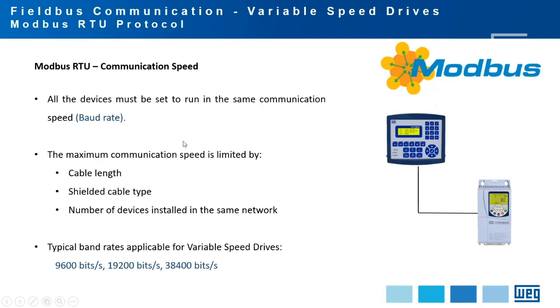Regarding communication speed, Modbus RTU requires all devices to use the same baud rate. The speed may vary according to cable length, cable type and shielding quality, and the number of devices in the network. Typical baud rates for variable speed drives go up to a maximum of 38,400 bits per second.